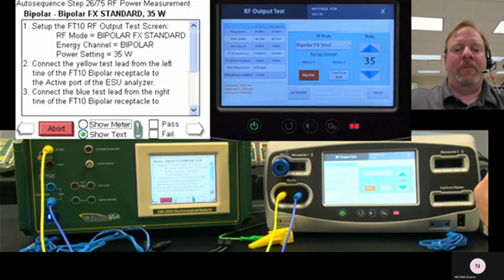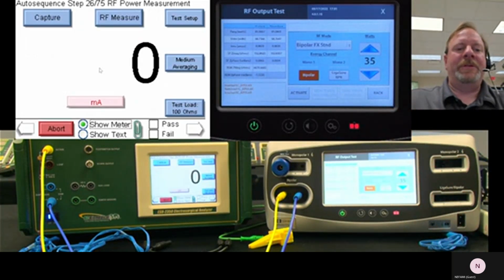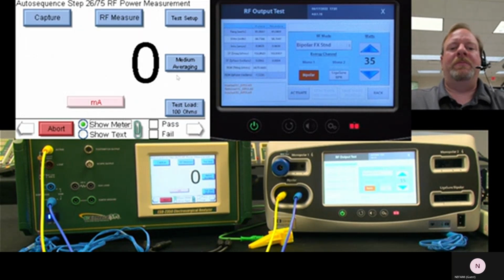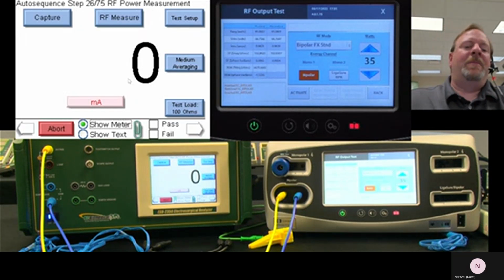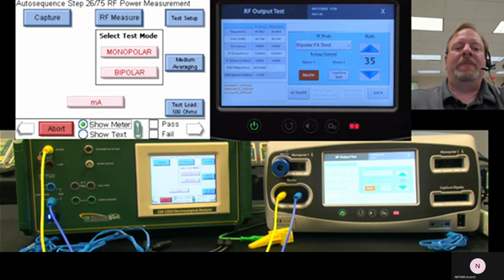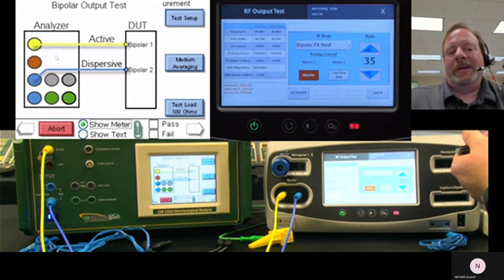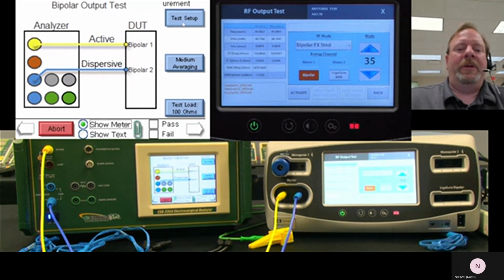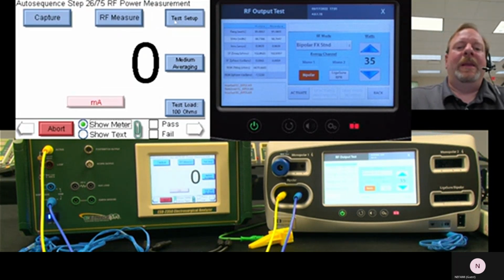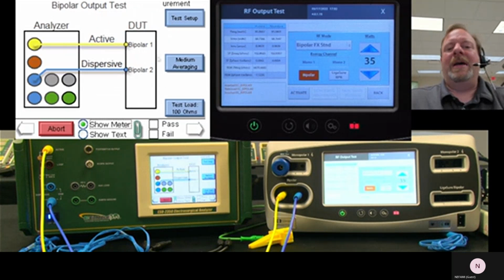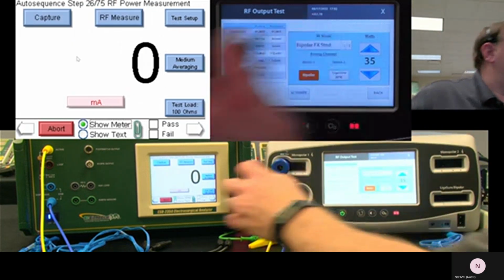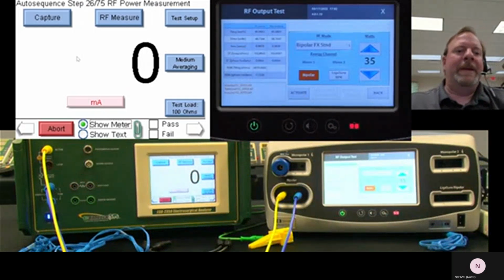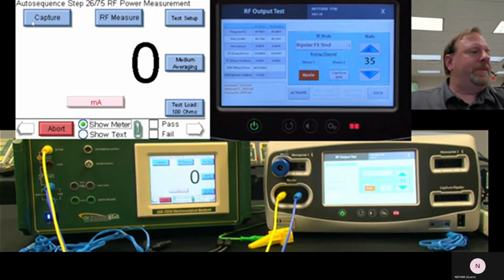Okay. Now, one thing, I mentioned the different averaging modes. This is set to medium averaging. Because I'm running an auto sequence, I can't change that. But if I do have any questions about the test setup, in this case bipolar, it does show me how to make the bipolar connections. This one says connect to the top of the blue. I'll just show you, it really doesn't change anything. Those are shorted internally. So we go to capture, and let's see.